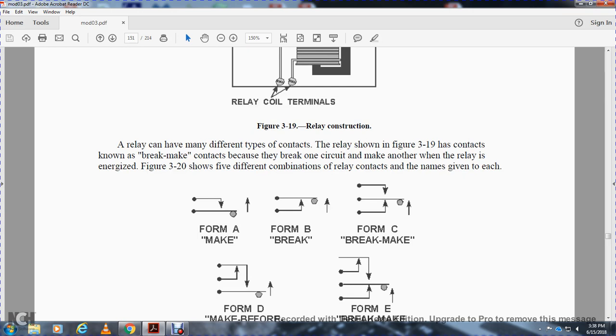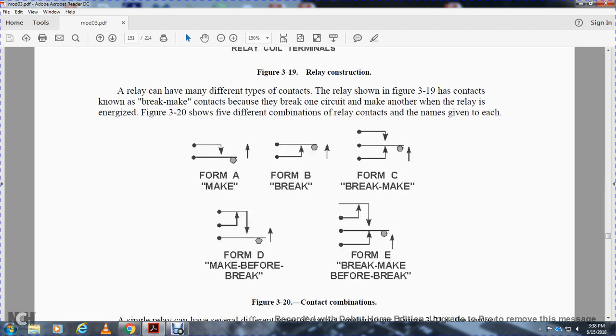A relay may have different types of contacts. The relay shown in figure 319 has contacts known as break and make, which may cause the break of one circuit of the relay with an energy change. Figure 320 shows 5 different combinations of relay contacts, with names given for each. Alright, form A is a make, form B is a break. Notice that one's down, one's up, make or break, or break make. Okay, and then the forms make before break and break make before break.